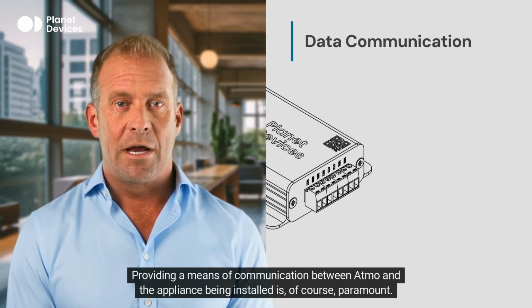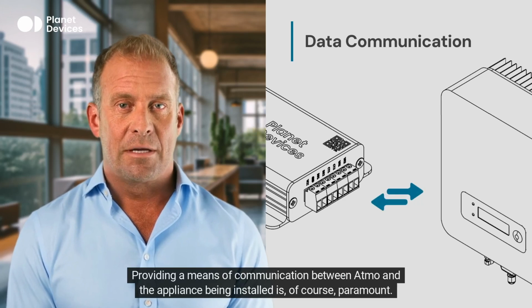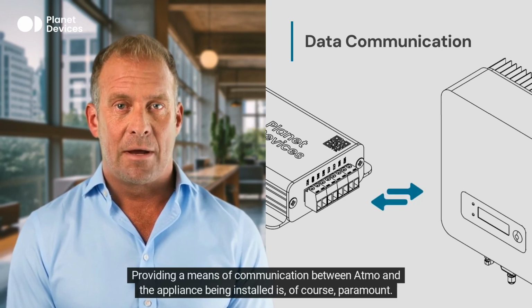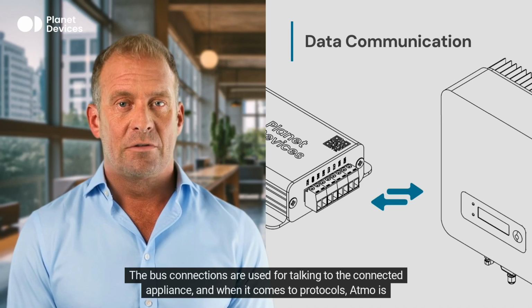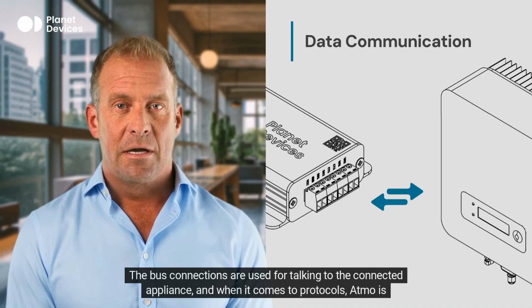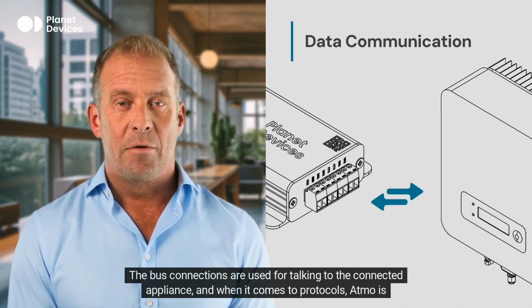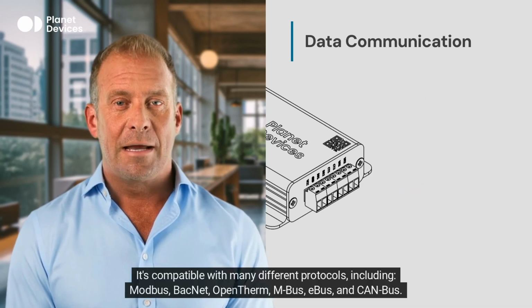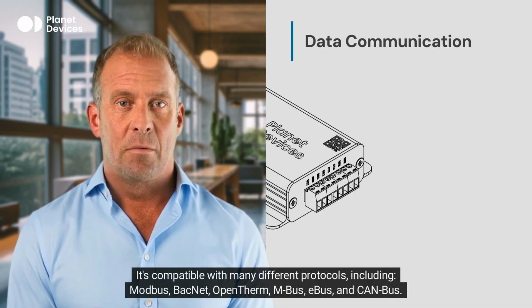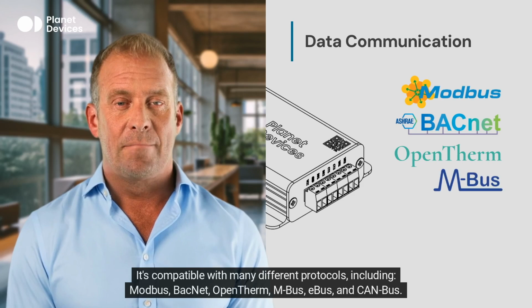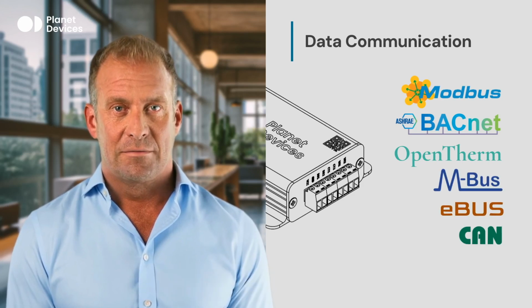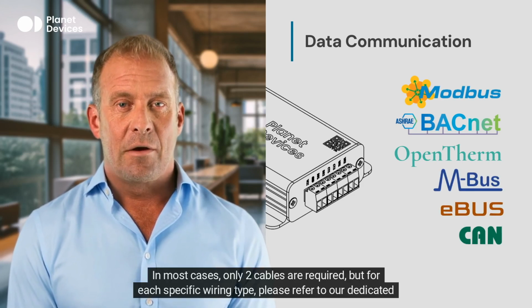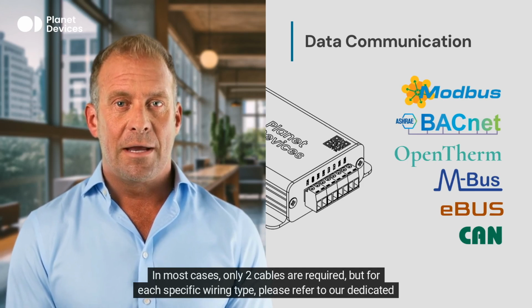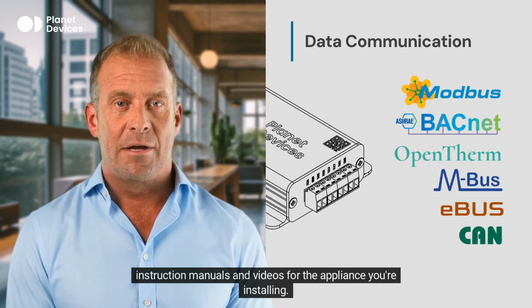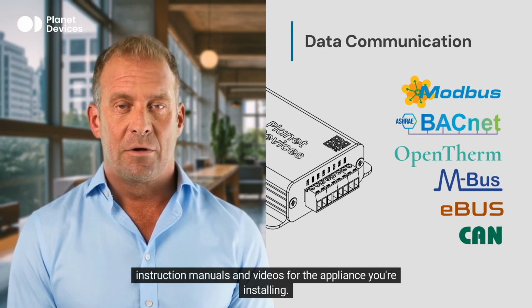Providing a means of communication between Atmo and the appliance being installed is, of course, paramount. The bus connections are used for talking to the connected appliance, and when it comes to protocols, Atmo is multilingual. It's compatible with many different protocols, including Modbus, BACnet, OpenTherm, MBus, eBus, and CAN bus. In most cases, only 2 cables are required, but for each specific wiring type, please refer to our dedicated instruction manuals and videos for the appliance you're installing.